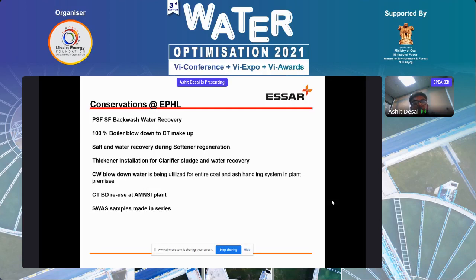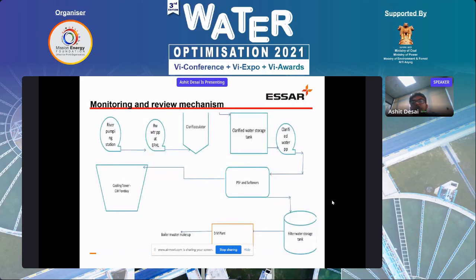All the SWAS samples, it's a small thing, but it makes a lot of difference. SWAS samples are made in series, like conductivity sample, we will divert it to pH and then dissolved oxygen, so that wastage of DM water would be minimized. This is standard power station chemistry. We have pumping station from river, raw water pump house, then clarifier water storage tank, to filtration plant which is used for cooling tower makeup, and DM plant used for boiler water makeup.